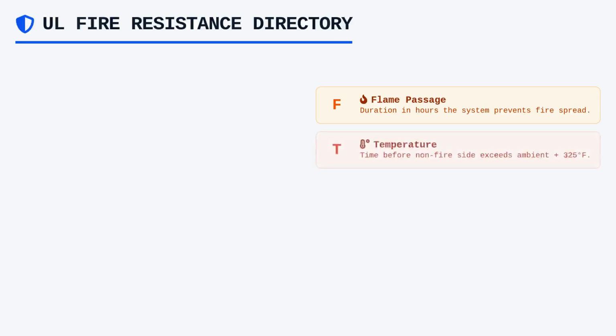The UL Fire Resistance Directory serves as our primary reference for selecting verified systems. Within this directory, we encounter specific ratings that guide our design choices. The F rating represents the duration in hours that the system prevents flame passage. We also look for the T rating, which indicates the time before the temperature on the non-fire side exceeds 325 degrees Fahrenheit above the ambient temperature.